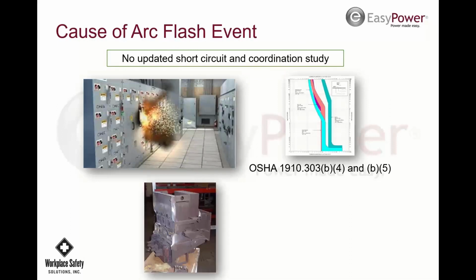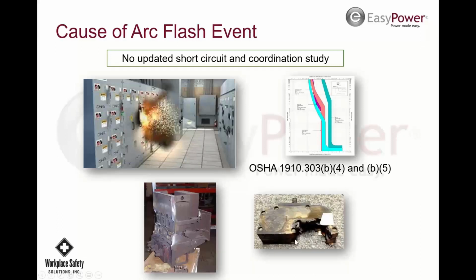This is going back to short circuit. So this is a 600 amp breaker that's rated for 35,000 amps in a 65,000 amp fault. So it's an old breaker. It was rated for the fault current at the time it was installed, but it's no longer rated. And it blows up, and it doesn't operate in the time current curve it's supposed to. Same thing here. It's a breaker that's rated for 10,000 amps and a 35,000 amp fault.